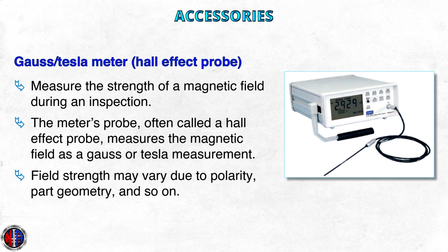Gauss/Tesla meter, also known as the Hall effect probe. Gauss or Tesla meters measure the strength of a magnetic field during an inspection. The meter's probe, often called the Hall effect probe, measures the magnetic field as a Gauss or Tesla measurement. The field strength may vary due to polarity, part geometry, and so on.